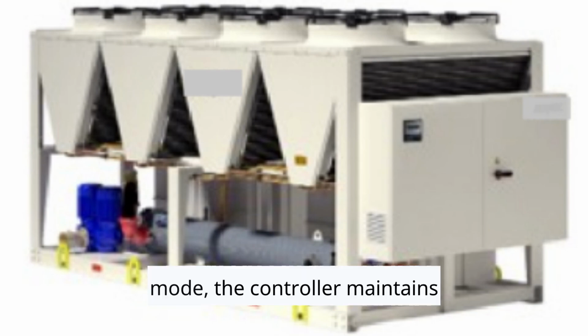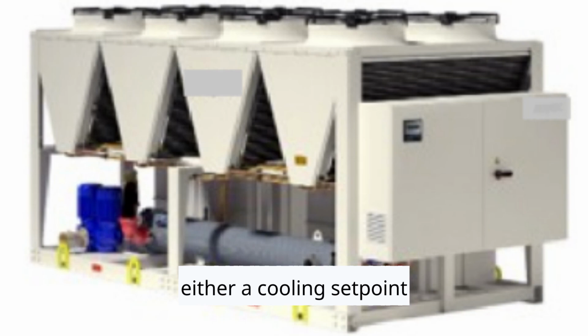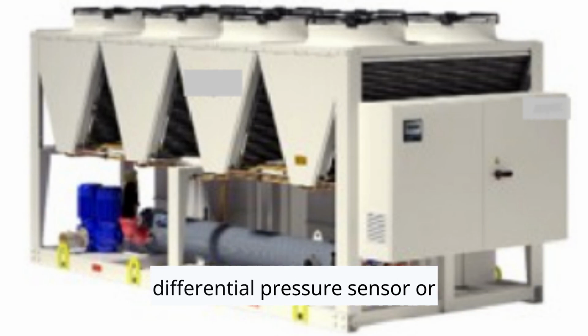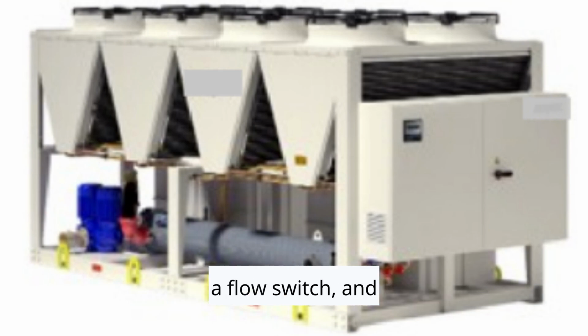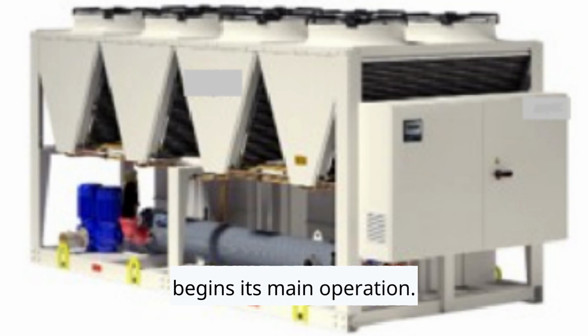Depending on the current mode, the controller maintains either a cooling set point or a heating set point. The system is always comparing the actual loop temperature with its target set point and differential. When proper flow is confirmed, either through a differential pressure sensor or a flow switch, and the loop temperature is beyond the set point plus its differential, the unit begins its main operation. Here's what happens step by step.